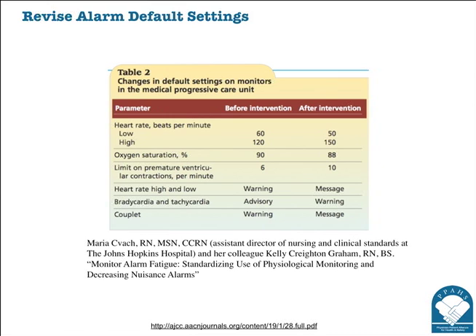That's adjustable by staff, up to a 15-second delay on nuisance alarms, meaning that if the patient's scratching or moving, it won't immediately alarm like it did in the past. That delay allows the patient to go back to their resting state and the monitor to read appropriately again. So my hat's off to the vendors for that.